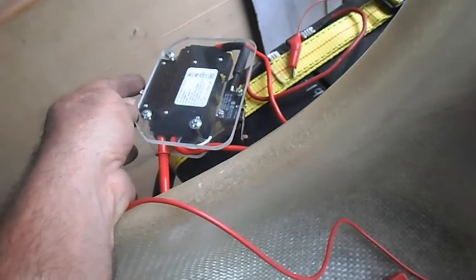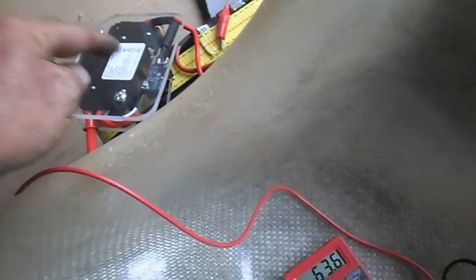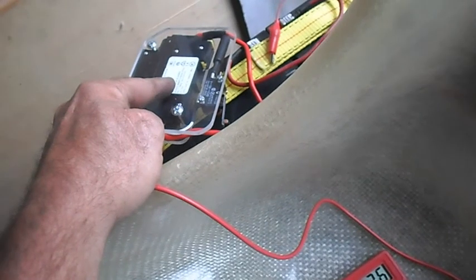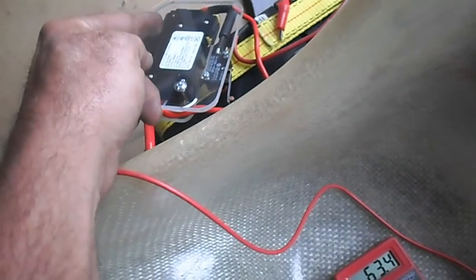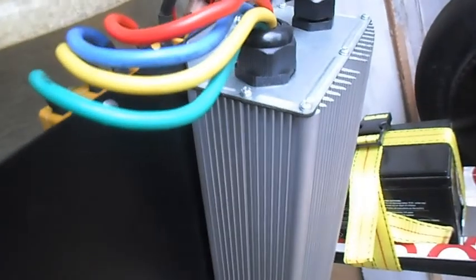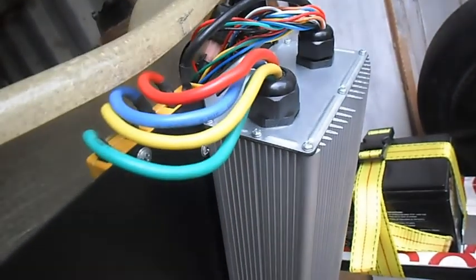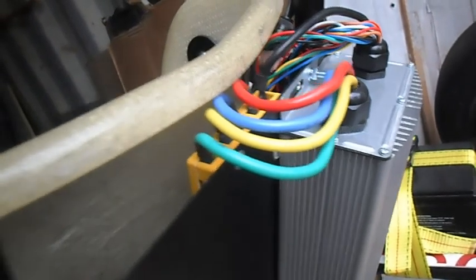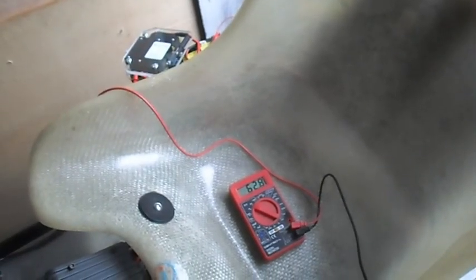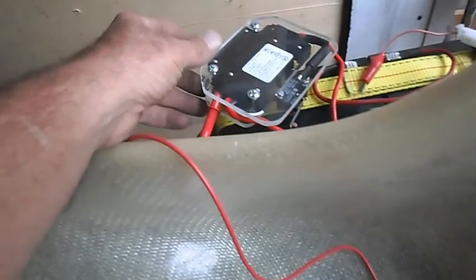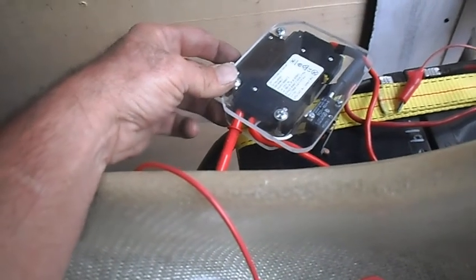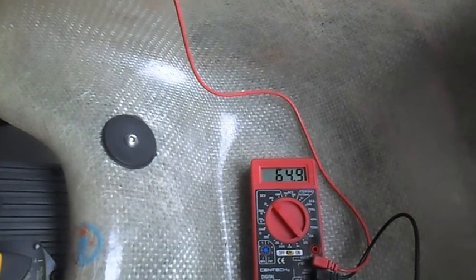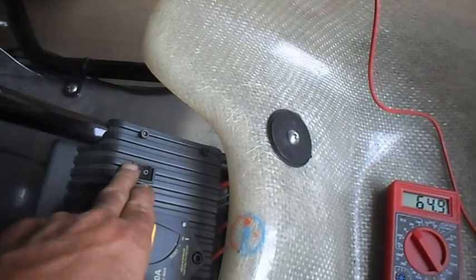This way, when the switch gets turned on now, the switch won't see a hard inrush of current across the contacts, and the capacitors in our speed controller won't see that huge inrush either, because they've already been filled up slowly with our precharge. Now we can turn our breaker on. The system is energized. Switch on.